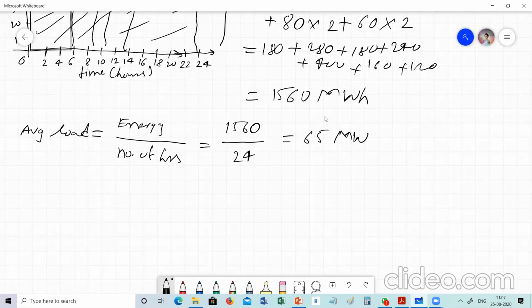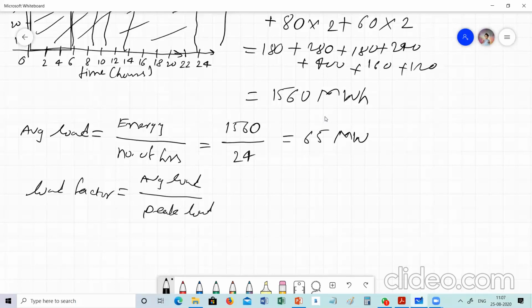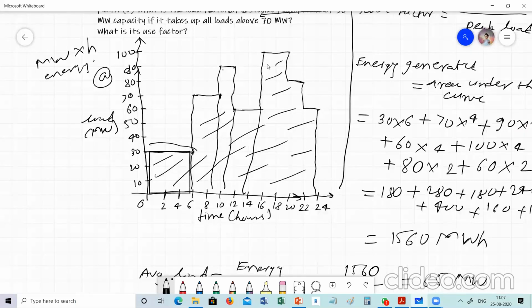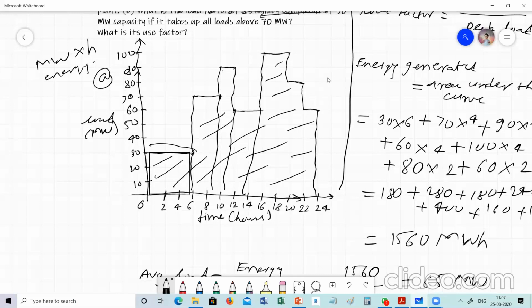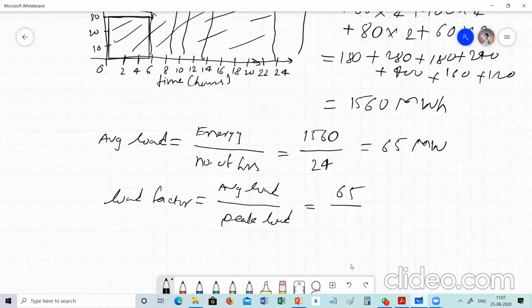Now we will calculate the load factor. Load factor equals average load divided by peak load. Average load is 65, and if we observe the graph, the maximum load is 100. So we divide 65 by 100, giving a load factor of 0.65.